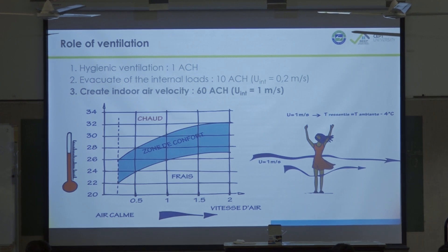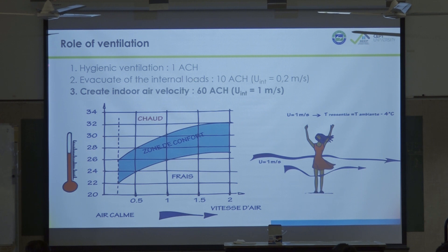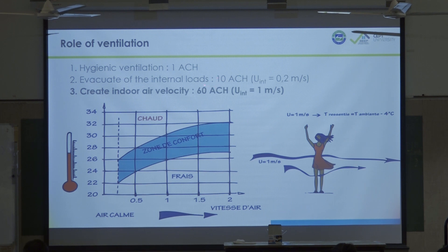This slide is very important — we will focus on steps two and three. For an air-conditioned building you need to renew the air at least one volume per hour — this is called one air change rate per hour. The second effect of ventilation is to release the internal loads, release the heat inside the building; in that case you need 10 air change rates per hour, and this generates an air velocity inside of 0.2 meters per second.